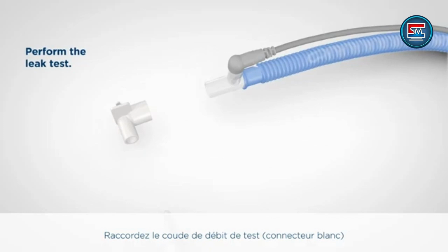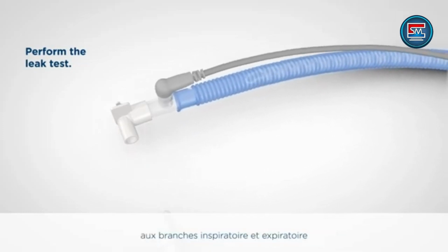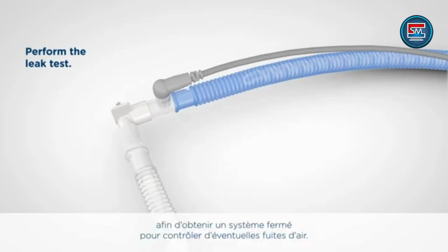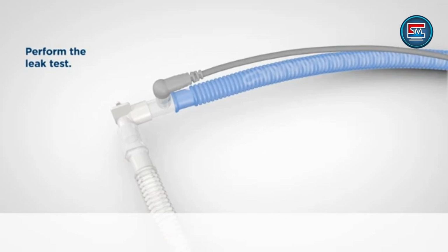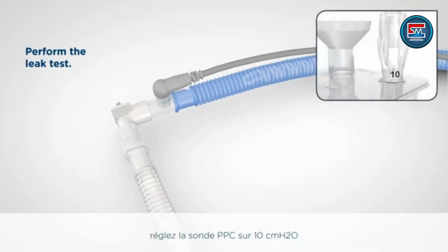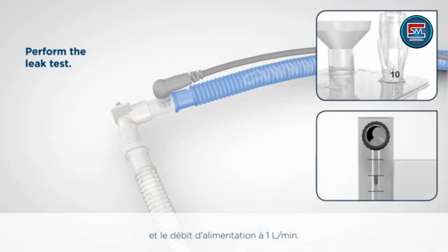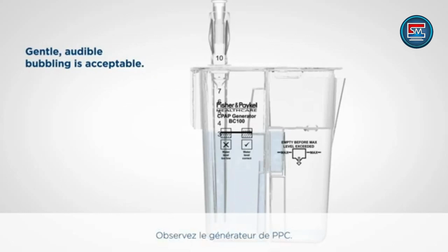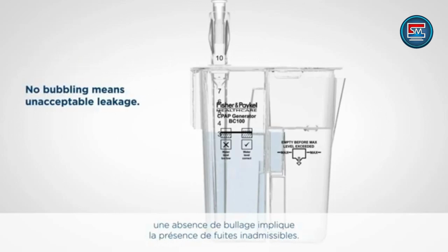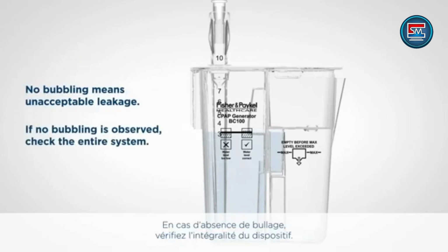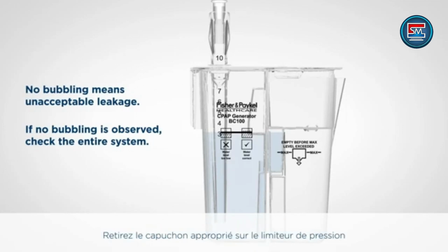Connect the test flow elbow, white connector, to the inspiratory and expiratory limbs to obtain a closed system for checking air leaks. Once the elbow is in place, set the CPAP probe to 10 centimetres of water and the input flow rate to 1 litre per minute. Observe the CPAP generator. Gentle, audible bubbling is acceptable. No bubbling means unacceptable leakage. If no bubbling is observed, check the entire system.